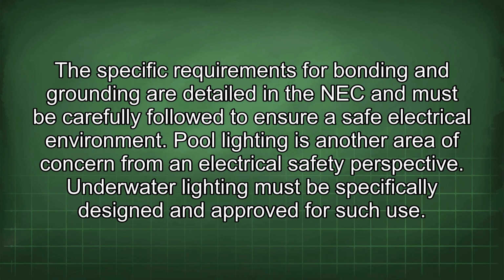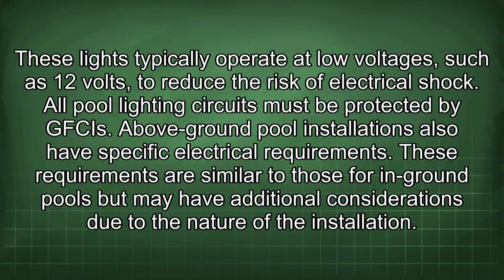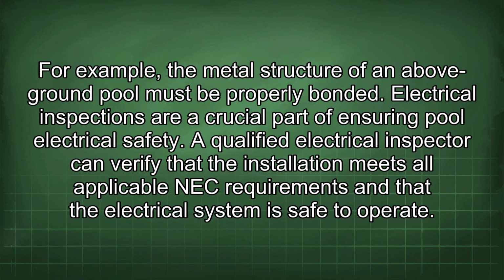Pool lighting is another area of concern from an electrical safety perspective. Underwater lighting must be specifically designed and approved for such use. These lights typically operate at low voltages, such as 12 volts, to reduce the risk of electrical shock. All pool lighting circuits must be protected by GFCIs. Above-ground pool installations also have specific electrical requirements. These requirements are similar to those for in-ground pools but may have additional considerations due to the nature of the installation. For example, the metal structure of an above-ground pool must be properly bonded.